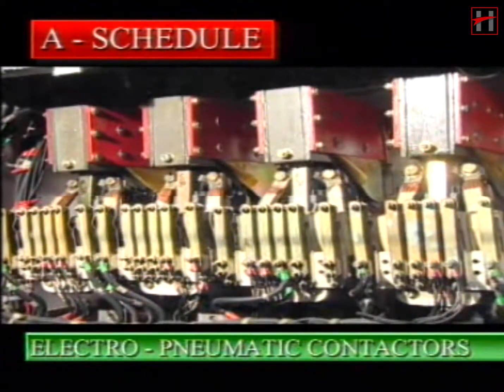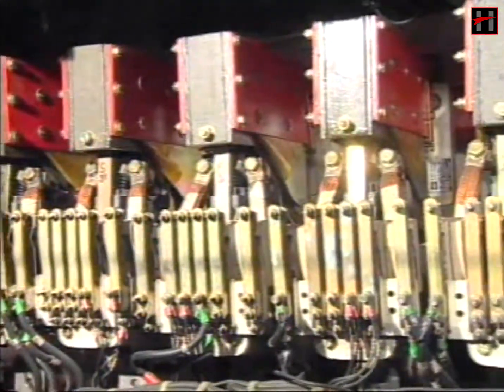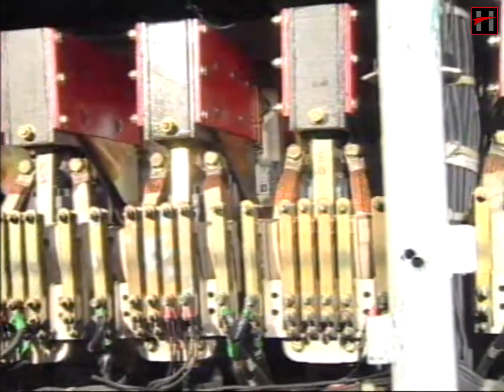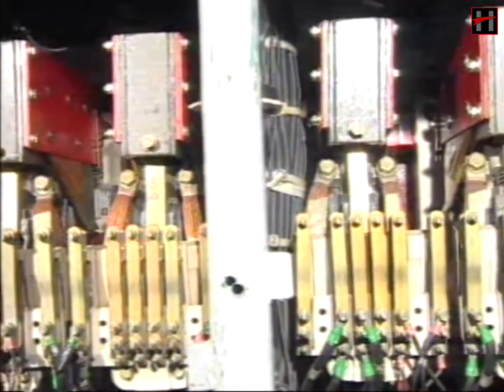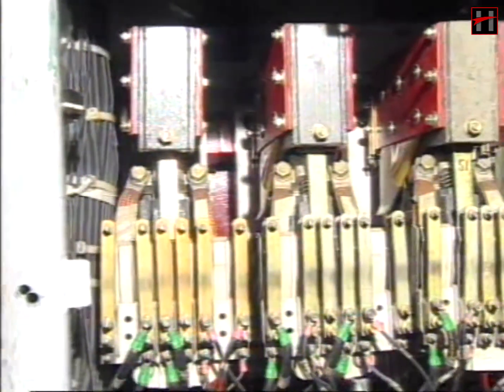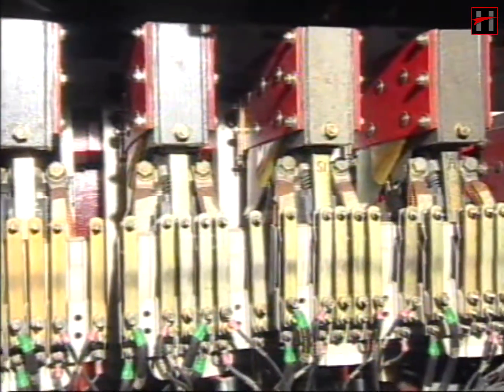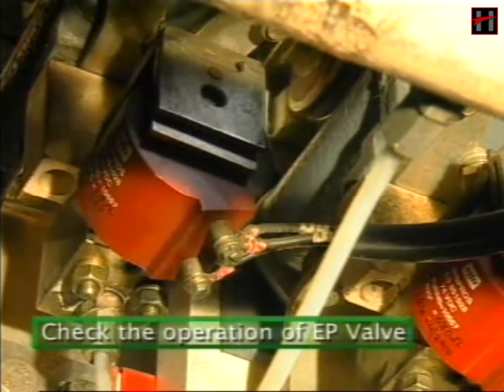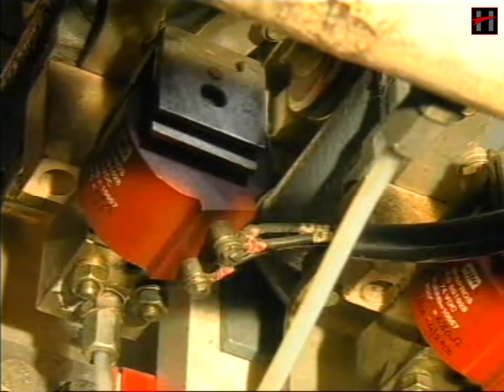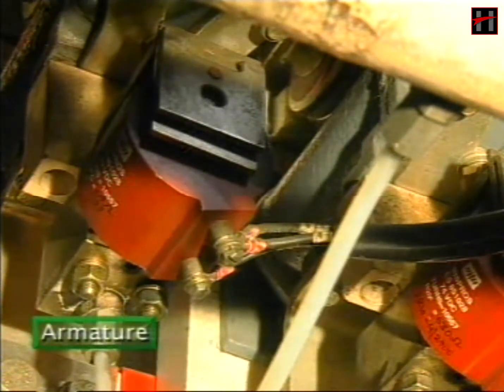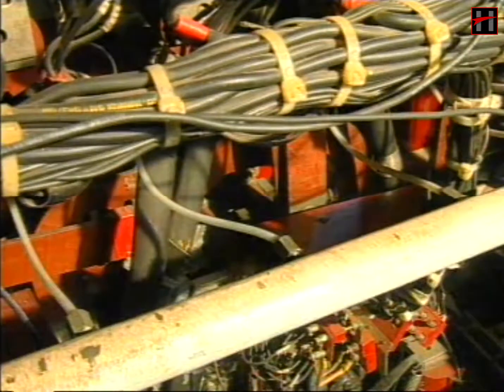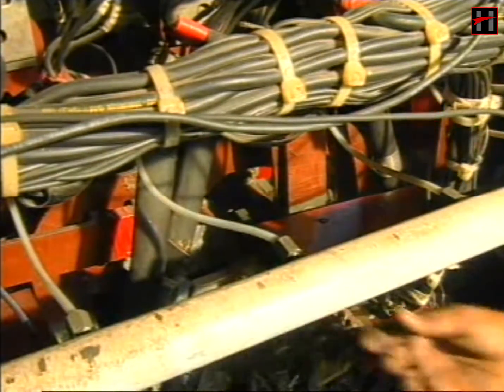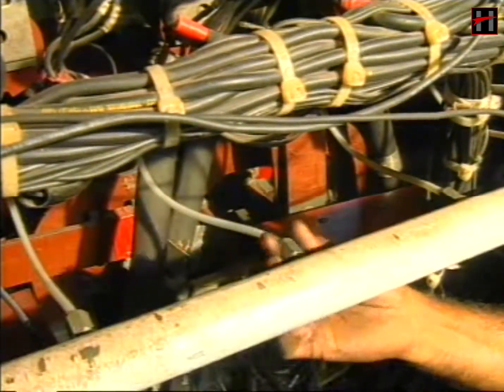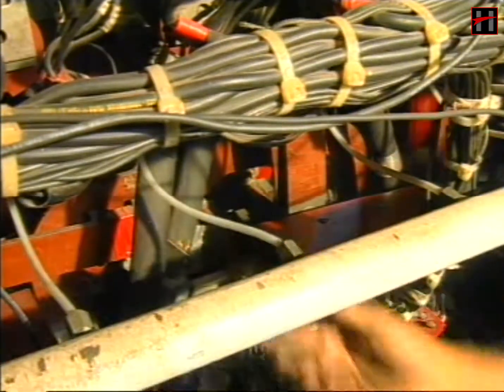Now we will talk about the maintenance procedure of the electro-pneumatic contactors. Check the contact tips, the shunts, terminal connections, interlocks, foundation bolts, and knuckling spring as shown to you in the case of electromagnetic contactors. In addition, check the operation of the EP valves of electro-pneumatic contactors in the engine start condition by pressing the armature manually. Ensure that there is no air leakage from the air pipes connected to the electro-pneumatic valves. If there is any air leakage, tighten the nut or change the pipe.